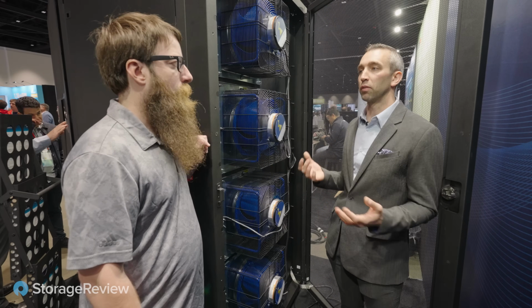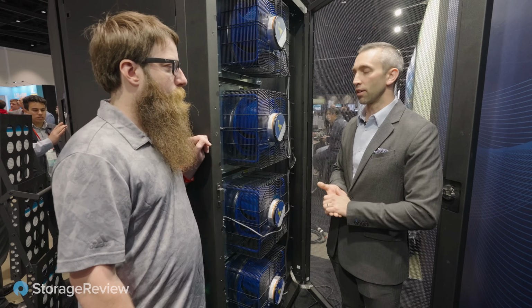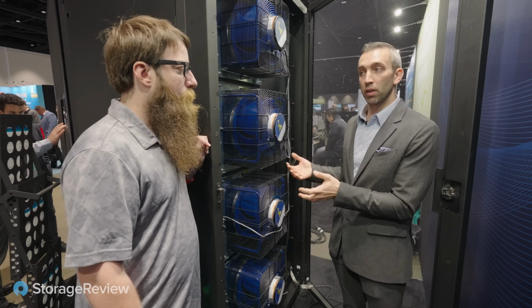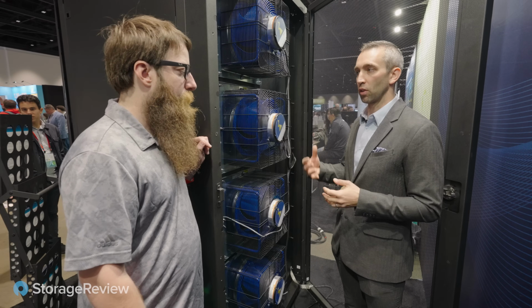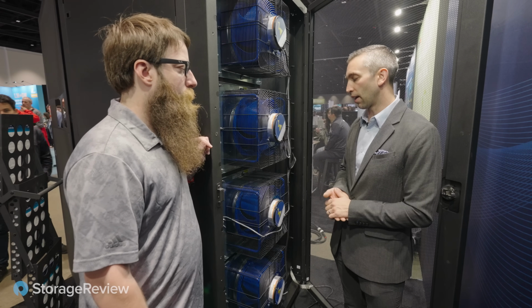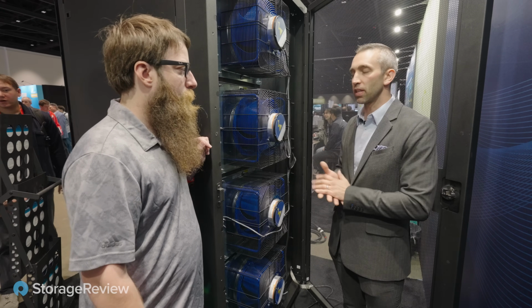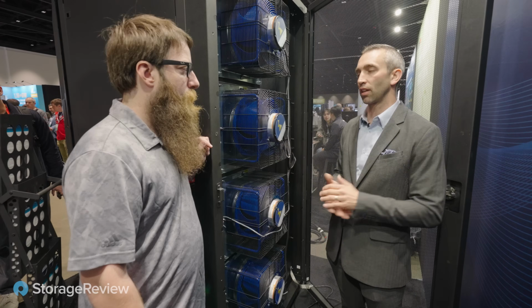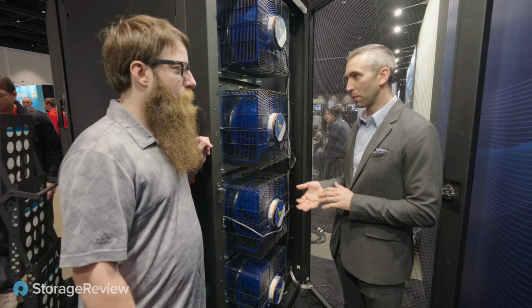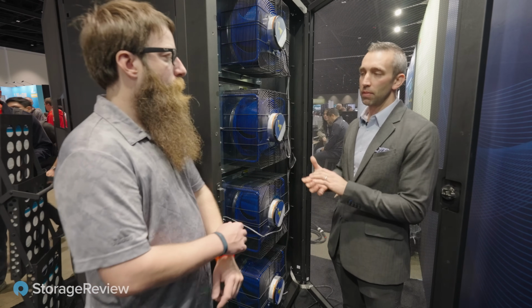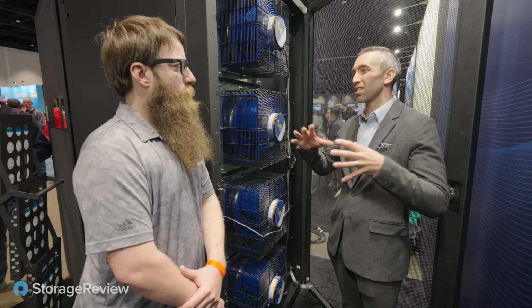Limiting factors might be airflow - they might have an airflow requirement we need to stay under. They might have a noise requirement so we'll keep the fans lower. They might have a heat load limitation where we can only connect so many racks to that system, or they might be flow limited. Our team at CoolIT is experienced with helping customers size that system.